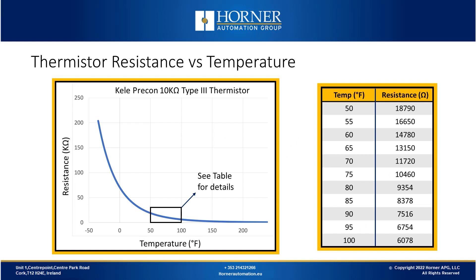Now we'll look at the thermistor resistance versus temperature curve shown in the middle of the screen, and we can see that it's an exponential relationship. The temperature ranges shown are approximately minus 50 degrees Fahrenheit to about 240 degrees Fahrenheit, with resistance going over 200K ohms and well below 1K at the high end. On the right, we can see a segment of the thermistor chart covering 50 to 100 degrees Fahrenheit — the ambient range very commonly used in indoor applications — and even in that limited range there's quite a difference in resistance.